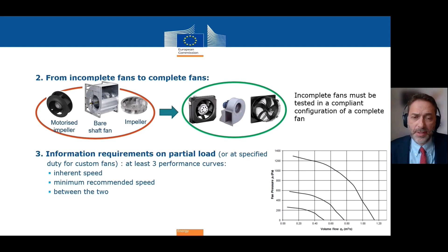Another important improvement is the introduction of information requirements on fan efficiency at partial load, at different flow and pressure, along three performance curves: one at inherent speed, another at minimum recommended speed, and one between the two. The purpose is to provide system designers with information on efficiency that enables them to optimize the system. We did the same for other products such as electric motors and variable speed drives, requiring information on efficiency at variable points of load and speed, in order to improve system design and reduce energy losses at the system level. That's very important.